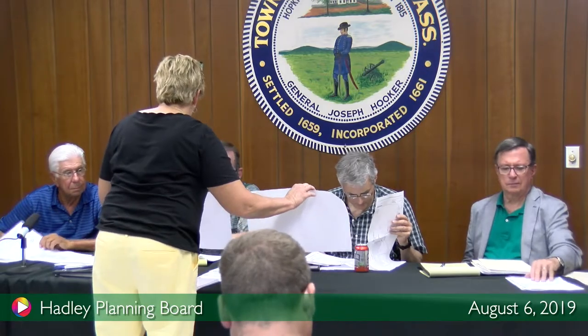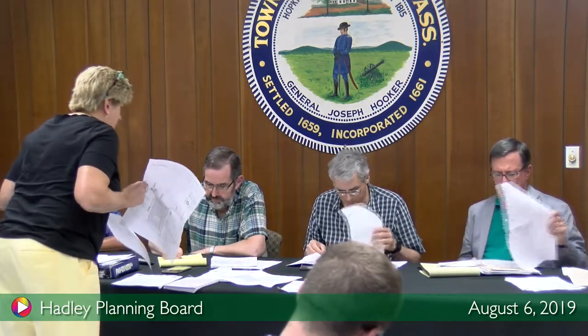So these two plans were from the original proposed, and the highlighted yellow is where the inverter for the current system goes. And on these plans that I provided you with, I highlighted the battery storage, which is right next to the inverter. So on both of the two pages, one showing north and one showing south, it shows you where the battery would be installed. So the battery storage unit is 35 feet long. It's 11 or so feet wide and 11 feet high. And it will just be installed next to the inverter.